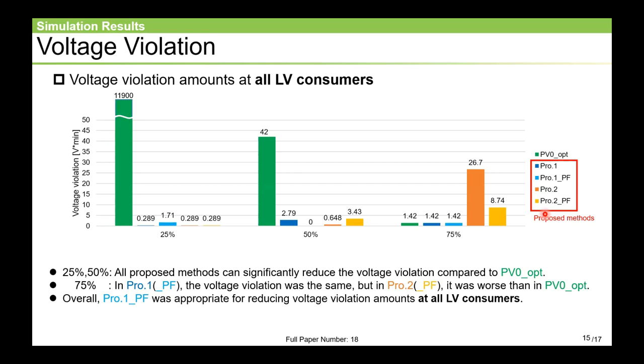However, the trend changes appeared when we look at the results of voltage violation at all LV consumers. First, at 25% and 50%, the voltage violation was significantly reduced for all the proposed methods. On the other hand, at 75%, PRO1 and PRO1_PF showed the same effectiveness as PV0opt, while PRO2 and PRO2_PF increased it. Overall, it can be said that PRO1_PF was appropriate for reducing the voltage violation amounts at all LV consumers.